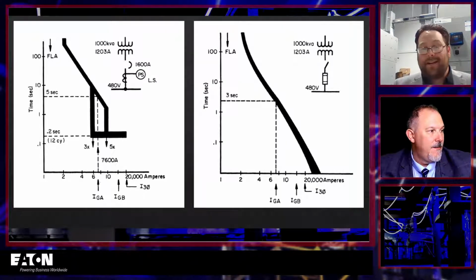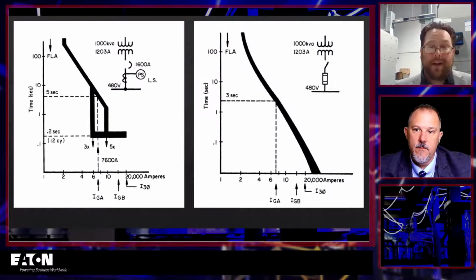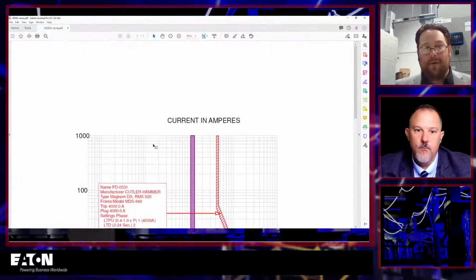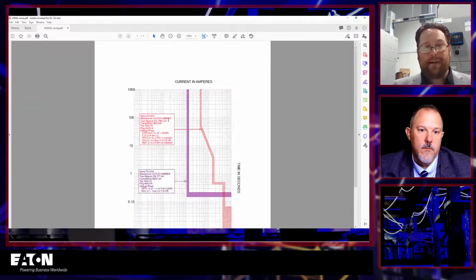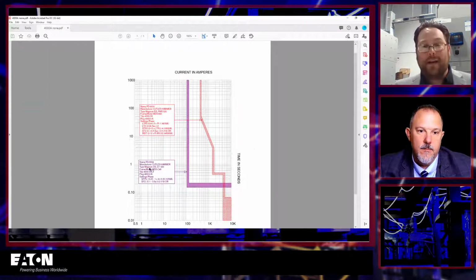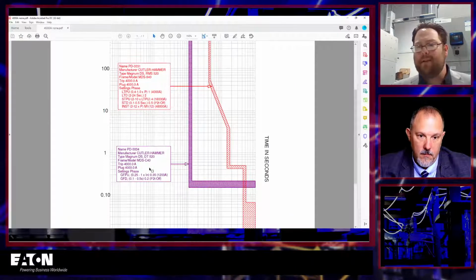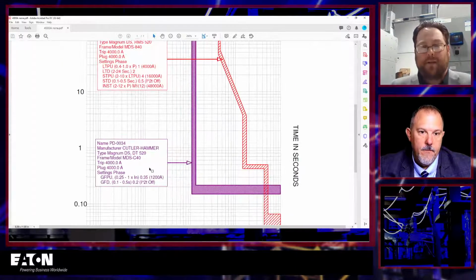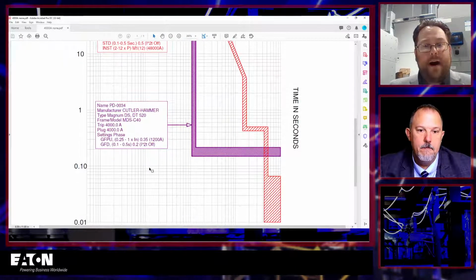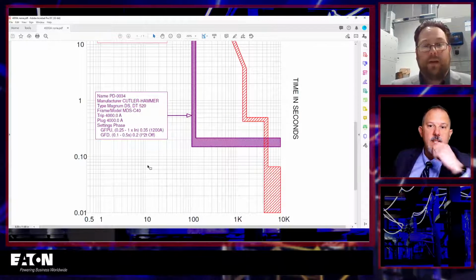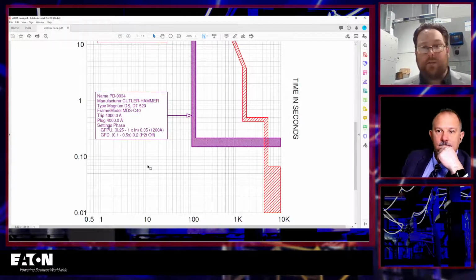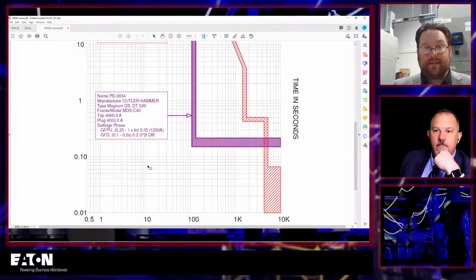typically your grounding conductor should have no current flowing on it, assuming a completely balanced system, which in my days in the field I don't think I ever found, but relatively close. Maybe you only have a few amps on it. But it's a much smaller current, and it offers a different way of ultimately coordinating our system, which we're going to talk about in a little bit, ground fault coordination.